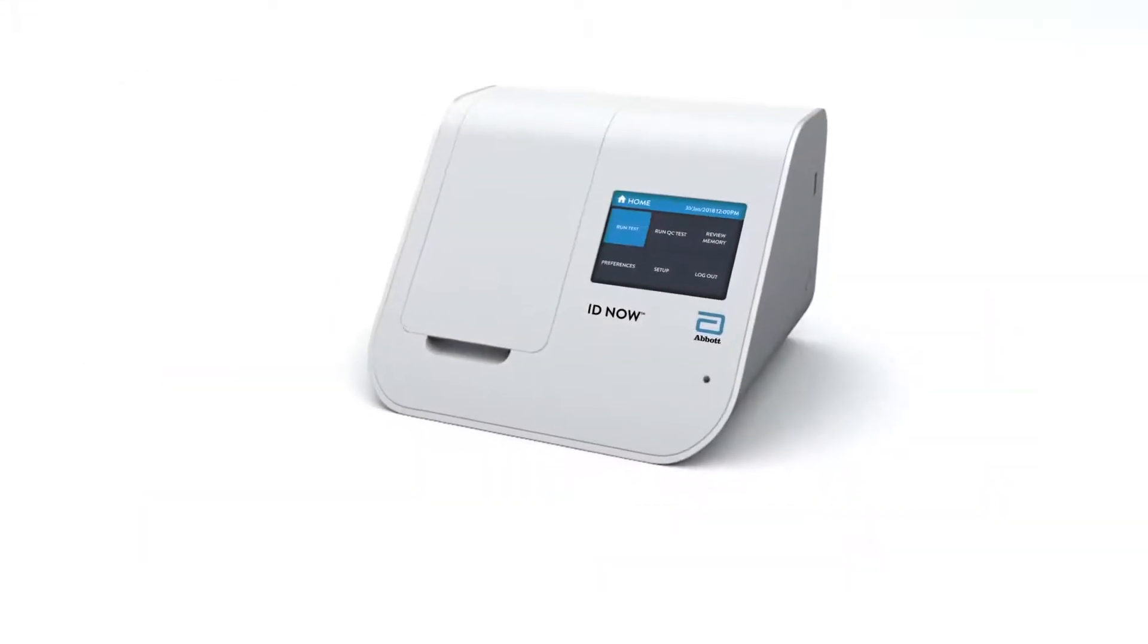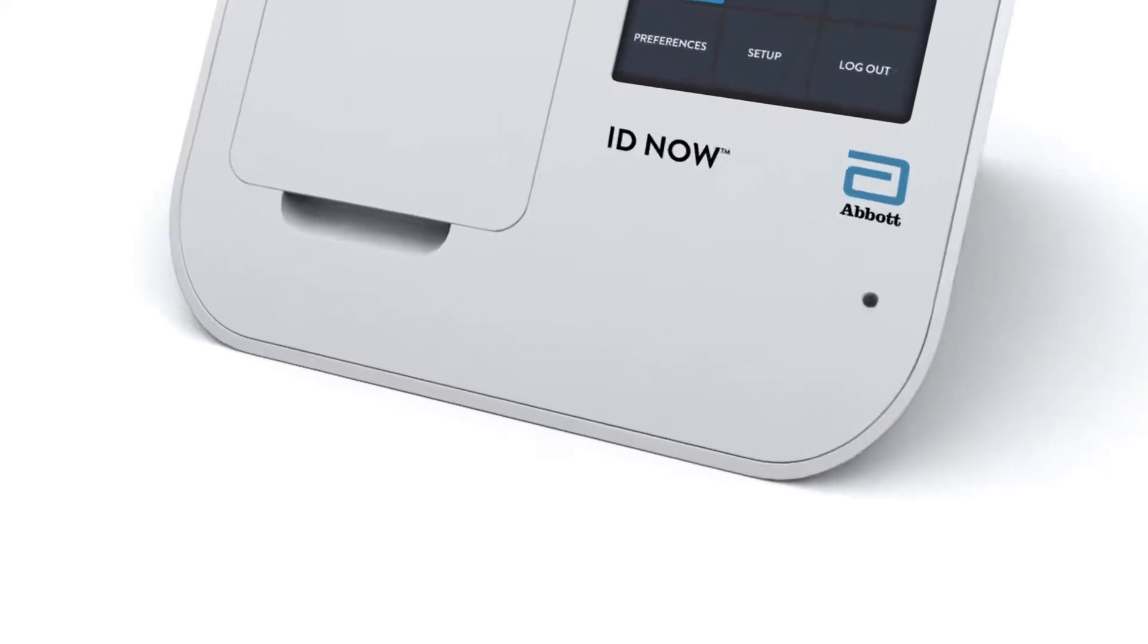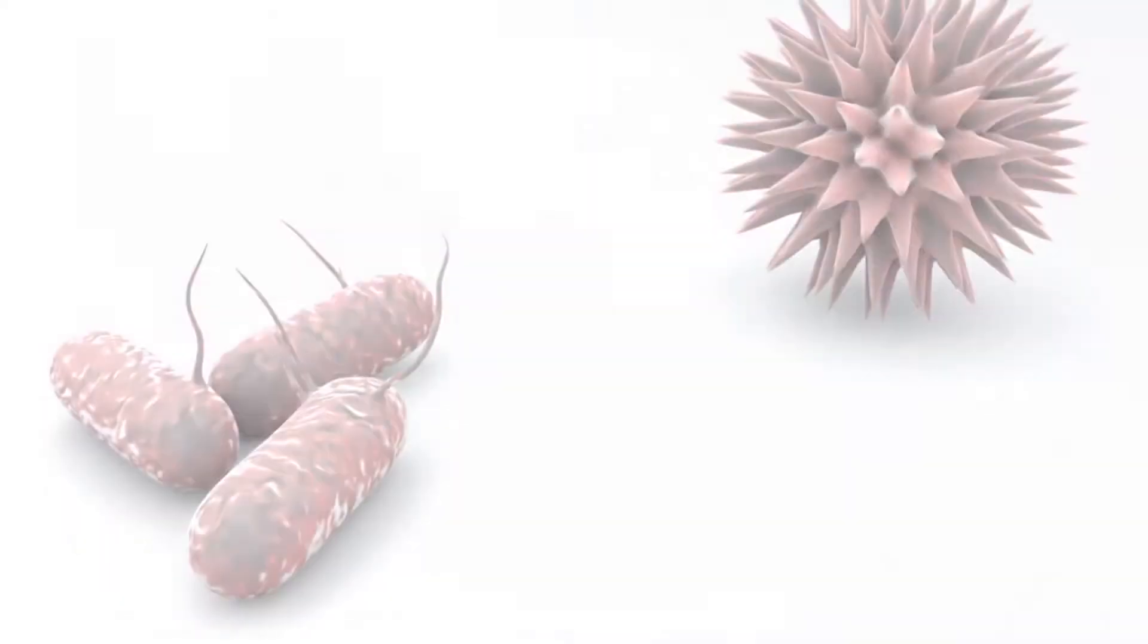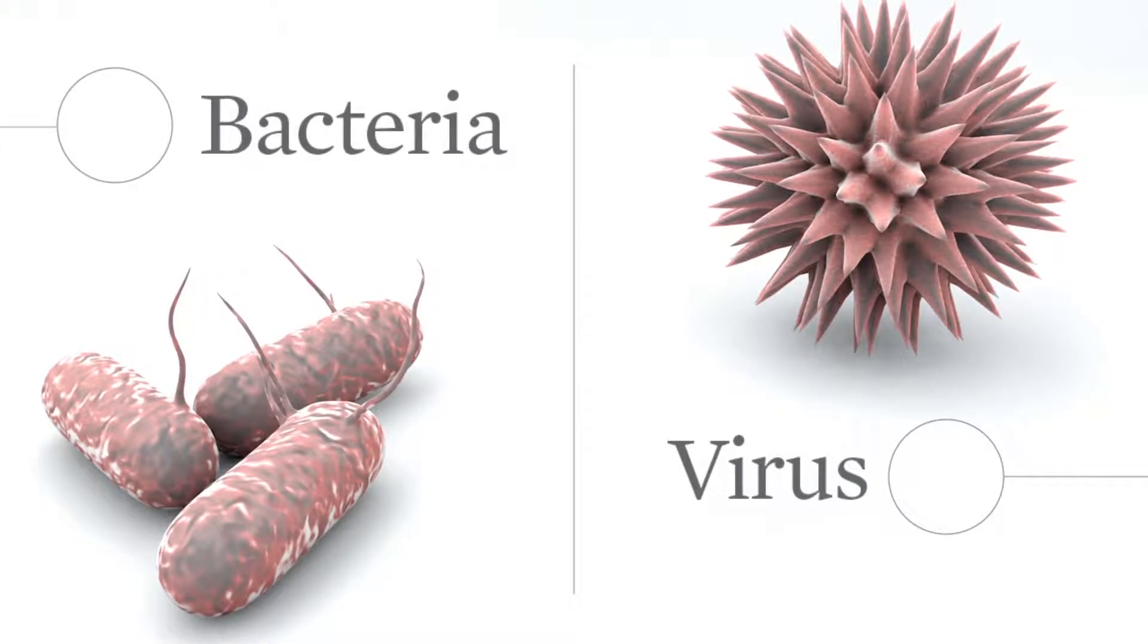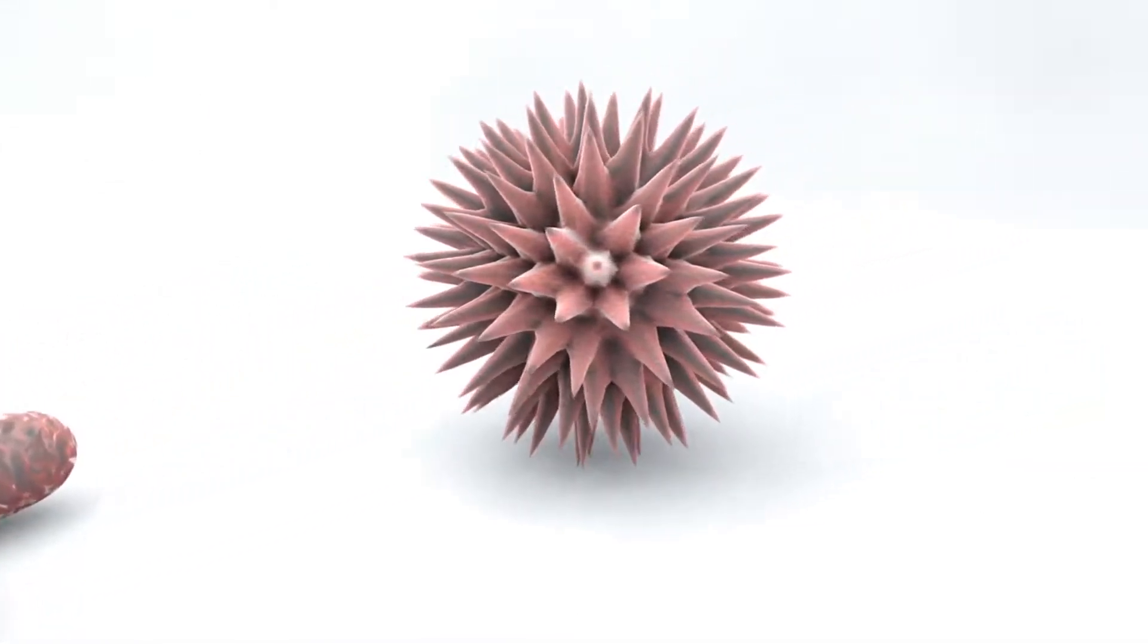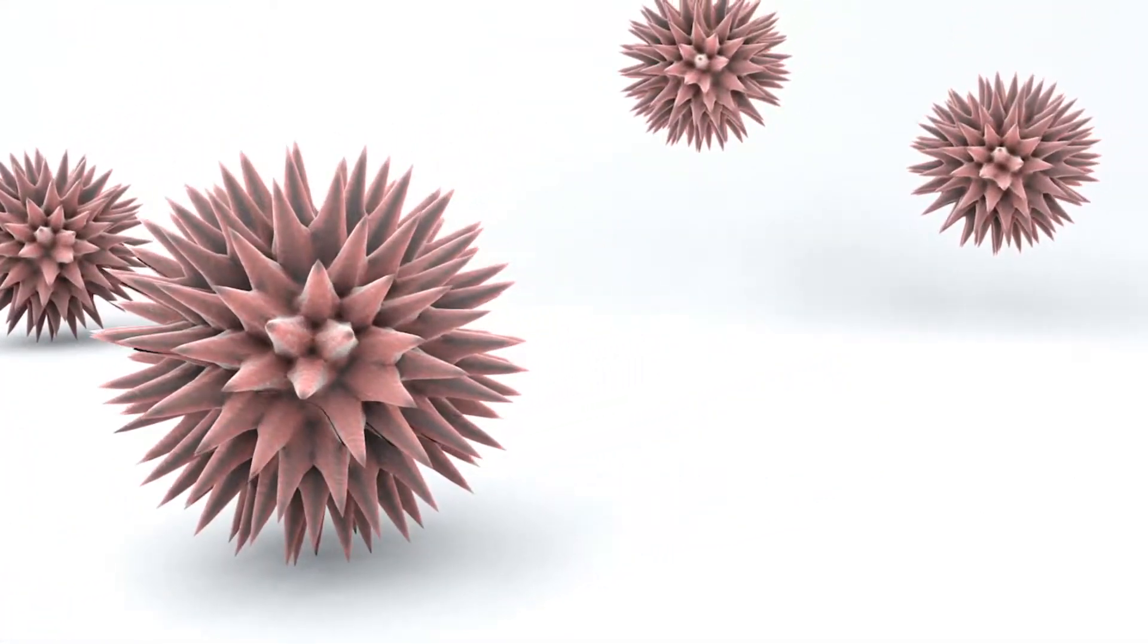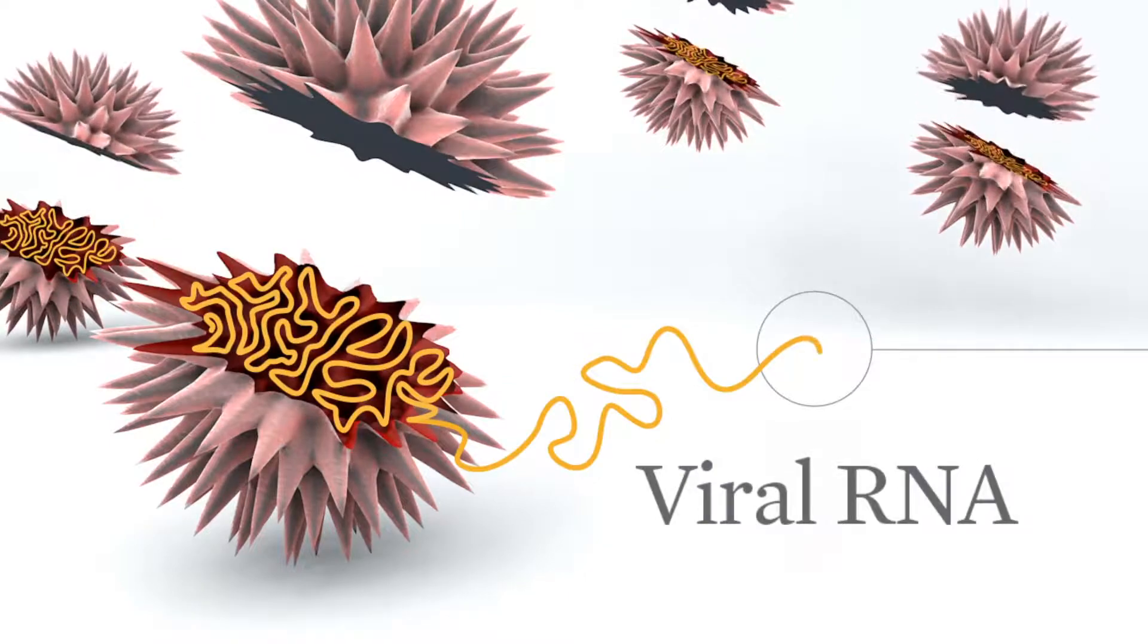How does the IDNow chemistry work? Let's take a look inside. After the sample is loaded, reagents in the test cartridge break open the viruses or bacteria, releasing the viral RNA and bacterial DNA.